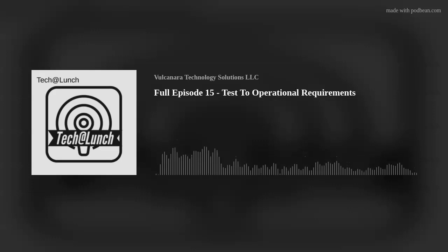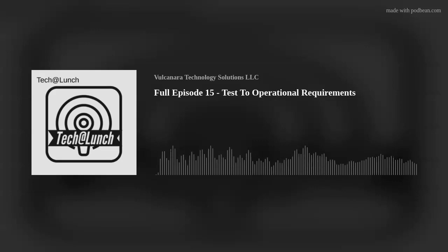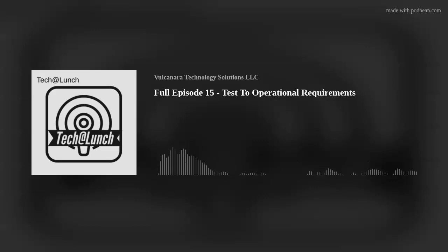So the first step is we have to have the requirements gathering. We have to have the parameters. The next step, once you have the parameters, is some type of QC check. With a QC check, you would basically say, here are the parameters, or here's the standard that we're going to go by. Anything that's outside of the standard: naming convention, using the right area in the data block, making sure that we're tying an FB and a DB to where it's supposed to be, making sure we don't have bits in there that are always on or always off.